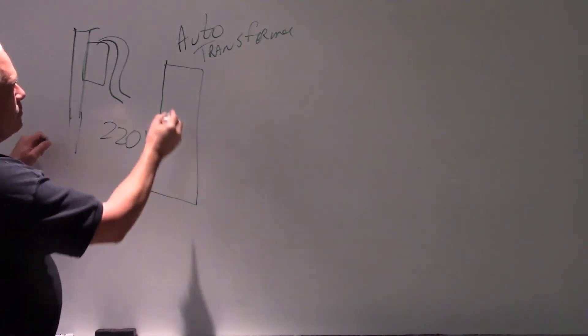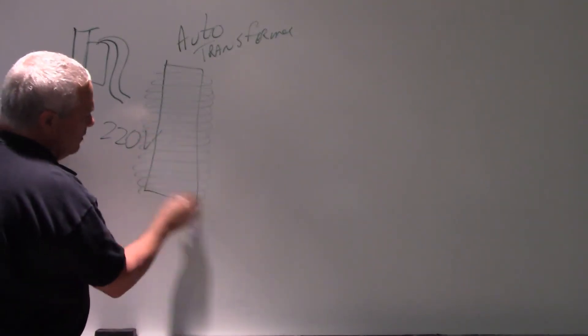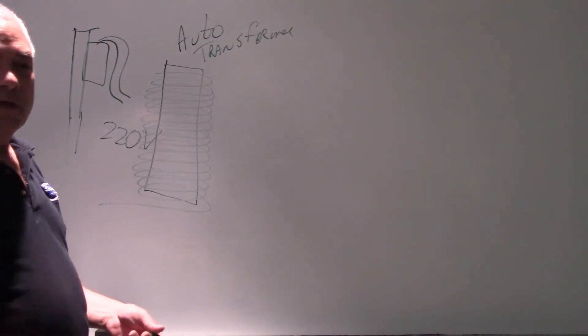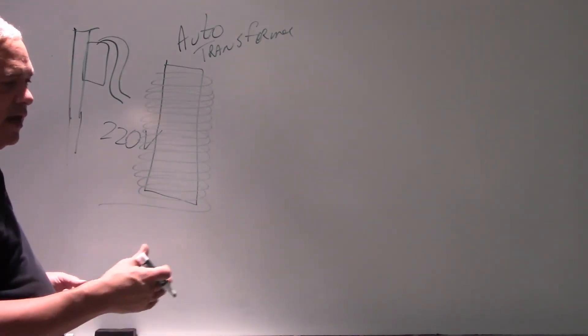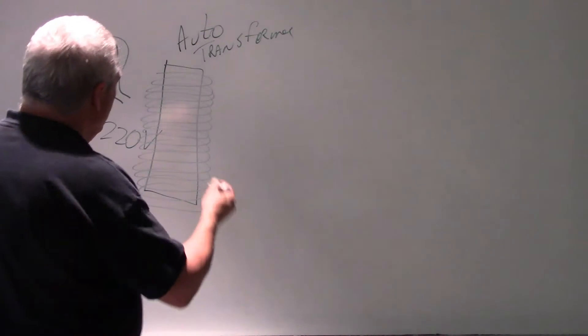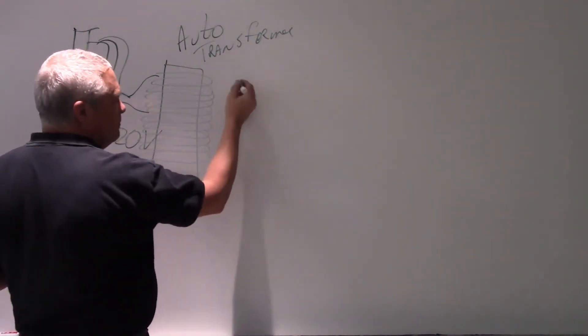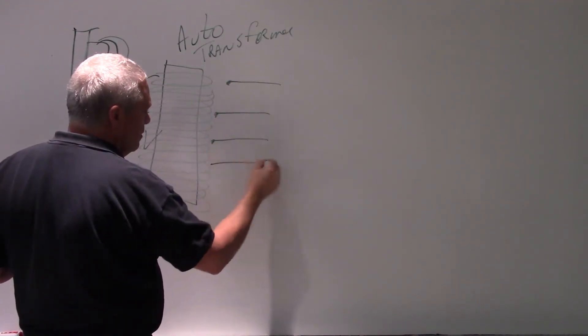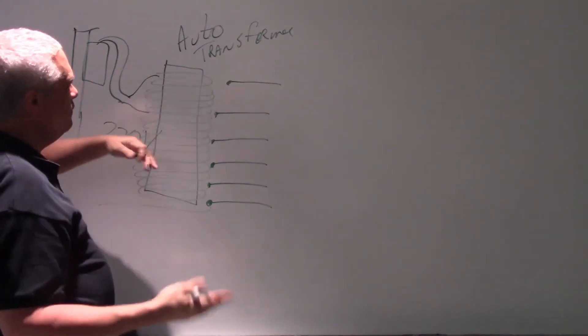The auto transformer is basically a lot of copper wire wound around a core — very simplistic. If you go on eBay and look for an auto transformer, you can buy one to play with. Basically, you plug it into the wall, and that transformer can either step up or step down the voltage. So you can have low voltage with high current, or higher voltage with lower current. The more coils the electricity passes through, the higher the voltage is going to be.